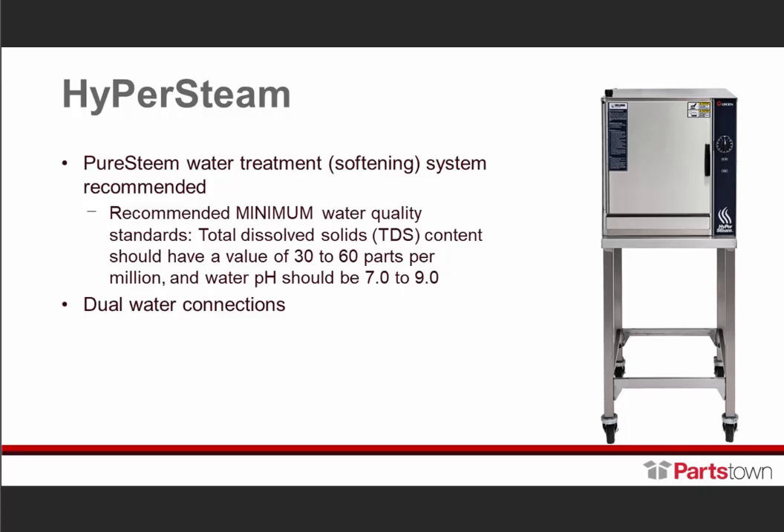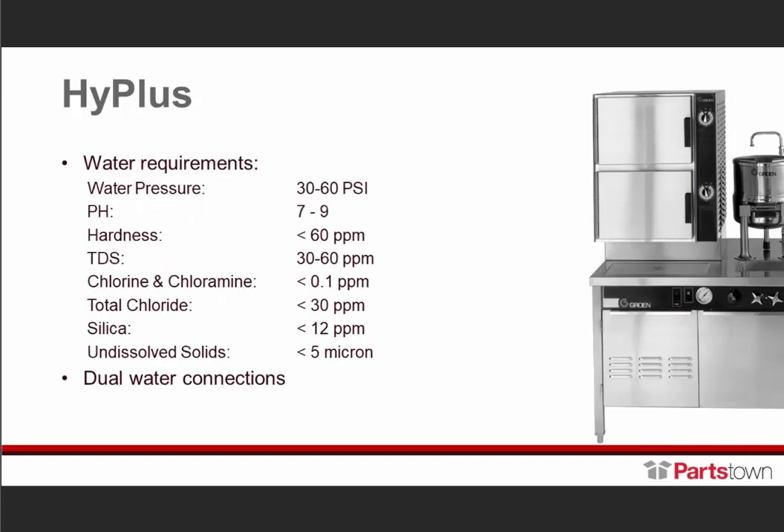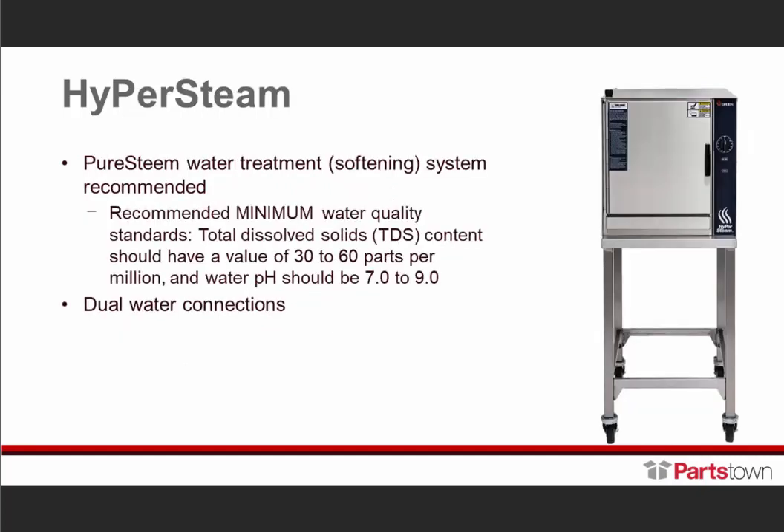One thing we recommend on this unit is — even if the water quality test comes back within our standards — we still recommend the PureSteem water treatment system. The main reason is that end users tend to neglect maintenance. They may not delim as often as they should, or not at all in some locations. So this will help, because even with water within standards, there's still the possibility of scale buildup. The Hyper Steam does require traditional deliming — there's a deliming port at the top left front where you add the deliming solution and press the delim button.